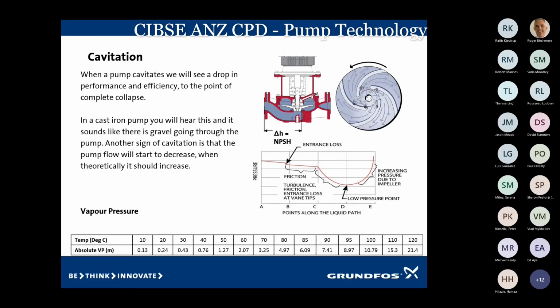When the water enters into the pump, as long as there's enough pressure to actually get into the pump and then overcome the net positive suction head requirement for the pump, it'll work. If we haven't got enough atmospheric pressure when it enters into the impeller eye to overcome the resistance of that impeller, that's when the water will turn to a vapor.